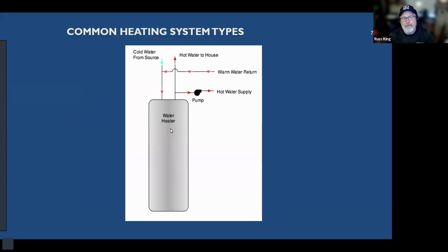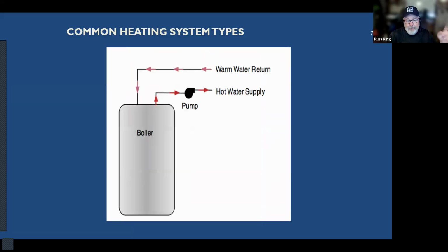And if your source is the same water heater that's providing domestic hot water for showers and stuff like that, we call that combined hydronic. Okay, combined hydronic, where the water heater is doing double duty. It's providing hot water for space heating, and it's providing domestic hot water for showers and washing dishes and stuff like that. But if your hot water source is only for space heating, we typically call that a boiler. All right. It just serves one purpose. So you have a separate hot water heater for domestic, and you have a boiler for space heating. Okay.